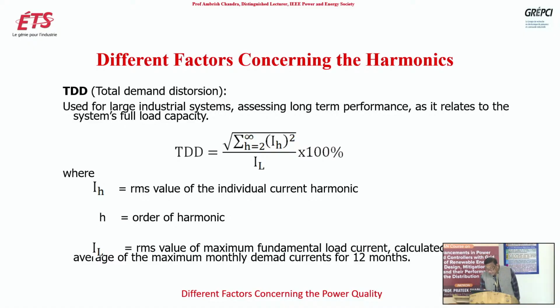But talking about TDD, this is for large industrial plants, and you can see the formula is the same as for THD, starting from the second harmonic. But here you see IL is the RMS value of the maximum fundamental load current, calculated as the average of the maximum monthly demand currents for 12 months. So instead of putting I1 here, which is the RMS current of the fundamental component, it is more complicated to calculate IL, and in some cases data may not be available, so it is not that easy to calculate TDD.